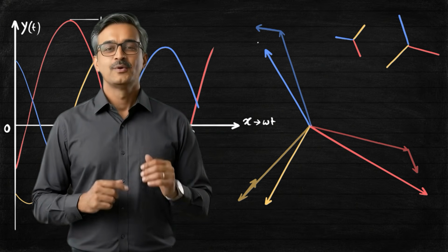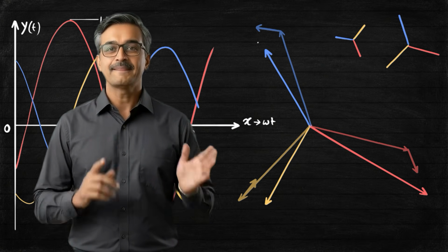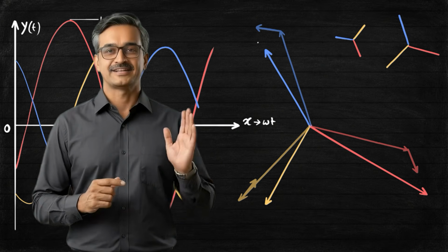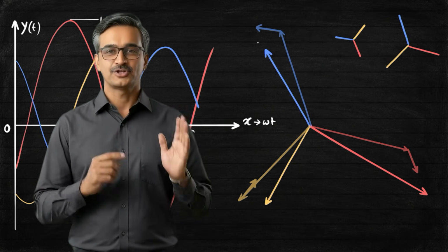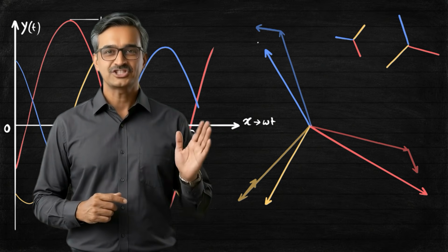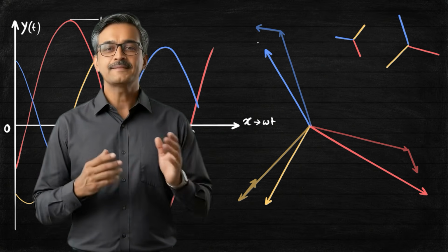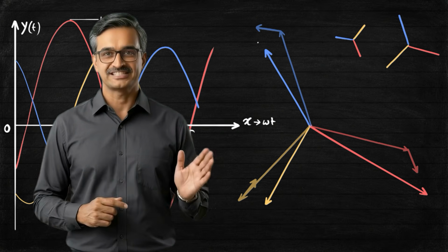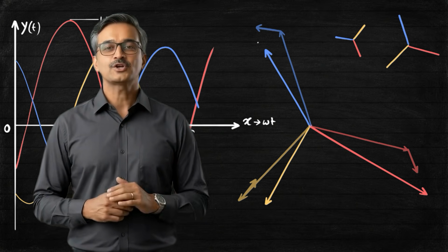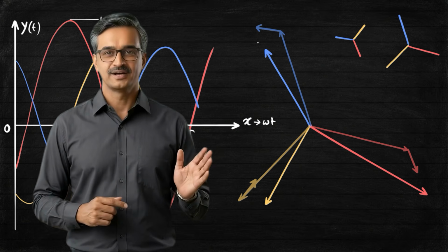But the negative sequence current can have an important effect on rotating machines. The negative sequence current set creates a reverse rotating magnetic field in the motor and thereby produces a backward torque in the motor, which may slow down the rotational speed of the motor or create disturbance in its rotation. In other words, it produces a reverse rotating magnetic field which can produce backward torque, heating, and disturbance in the smooth rotation of the motor.